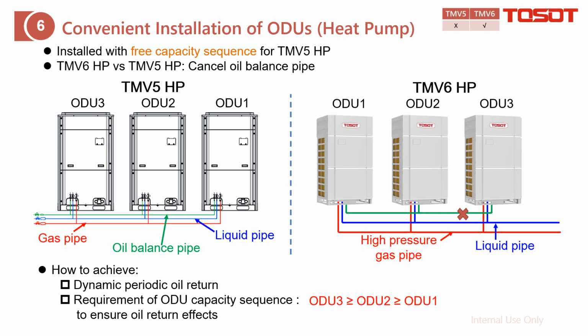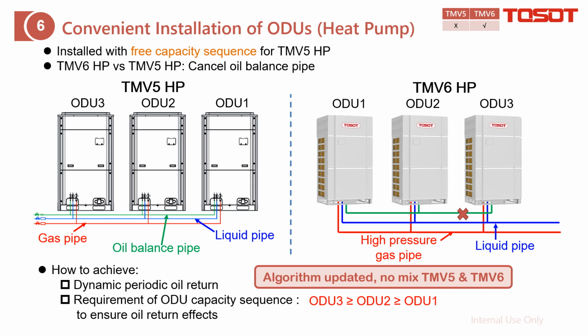On the other hand, if an outdoor unit has a larger capacity, it also requires the compressor to operate at a higher frequency. Higher frequency also requires more oil for lubrication. So we send more oil to this larger outdoor unit 3 for its greater oil requirement, which means our setting. Last but not least, as the algorithm was updated from TMV5 to TMV6, please never mix TMV5 heat pump or heat recovery with TMV6 heat pump or heat recovery.